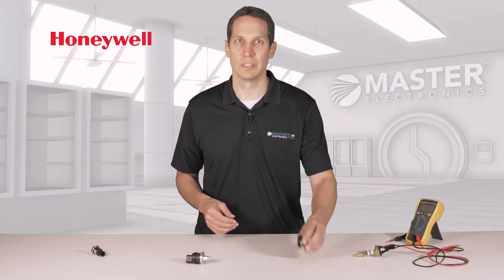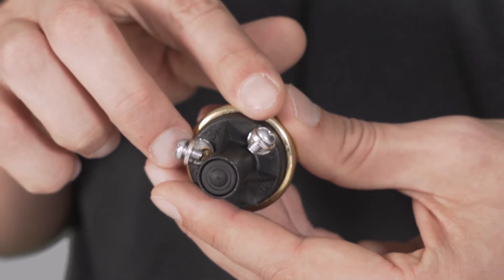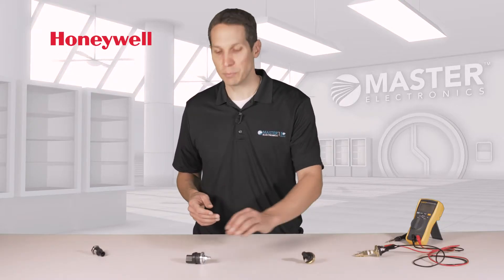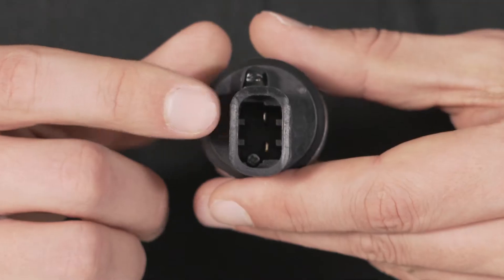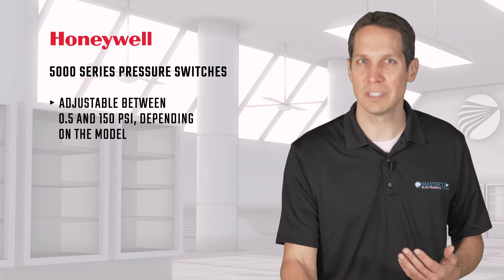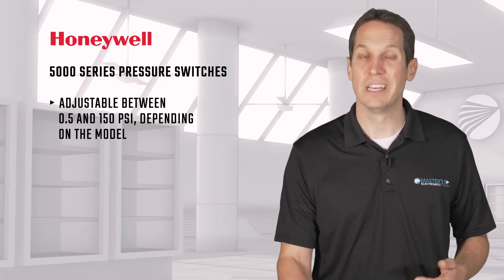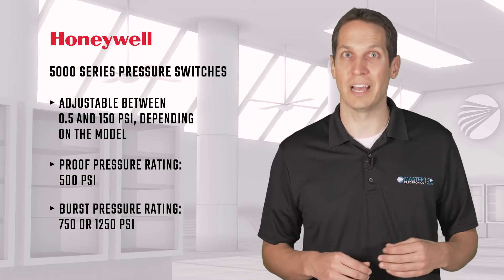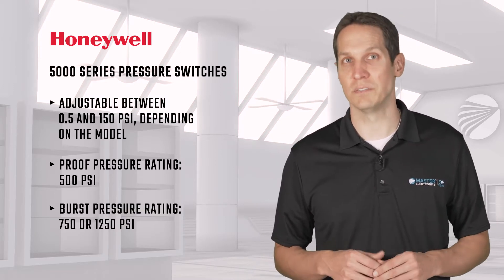There are different terminal options. This is a screw terminal, and it's great due to its ease of use and flexibility. But there are also the Metri-Pack connector versions if you need a tight seal on the termination end. These are adjustable from anywhere between 0.5 and 150 psi, depending on the model you get, and have proof pressure ratings of 500 psi and burst pressure ratings at either 750 or 1250 psi.